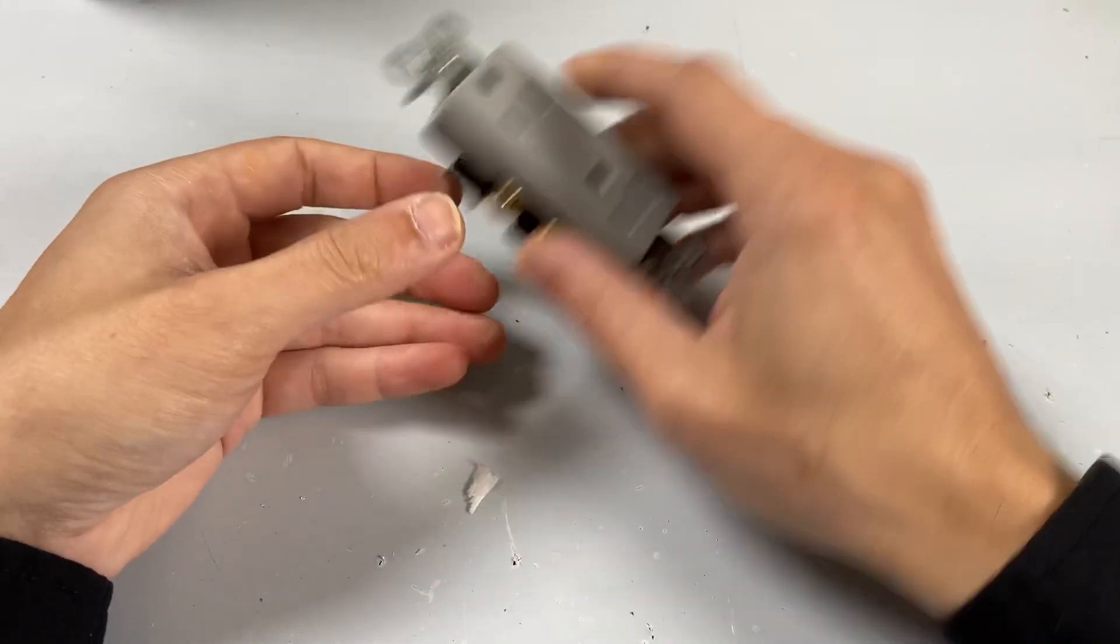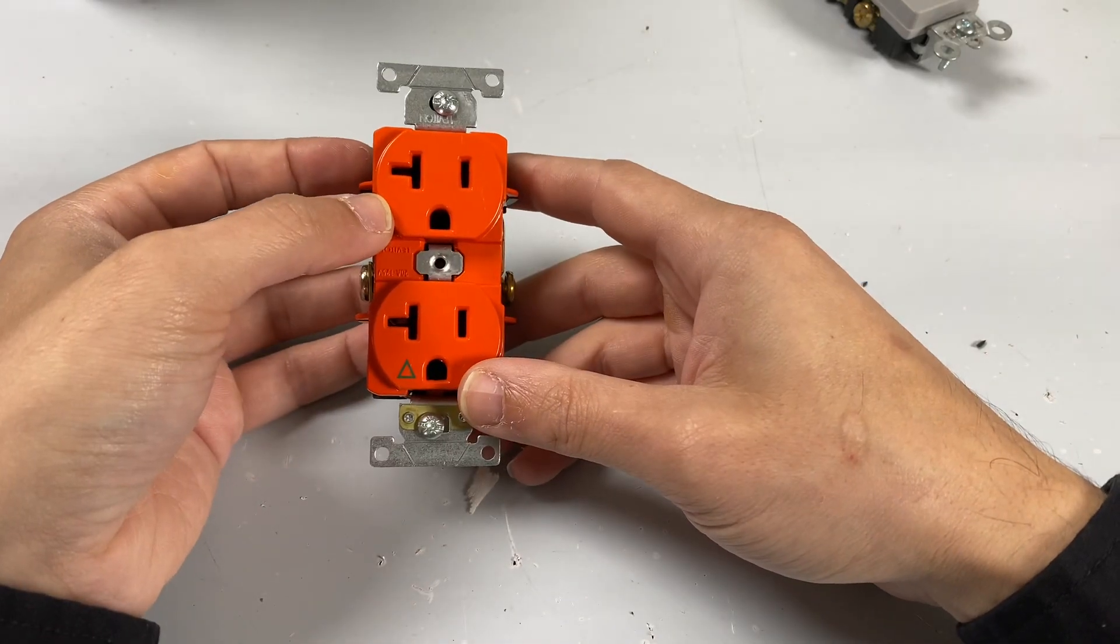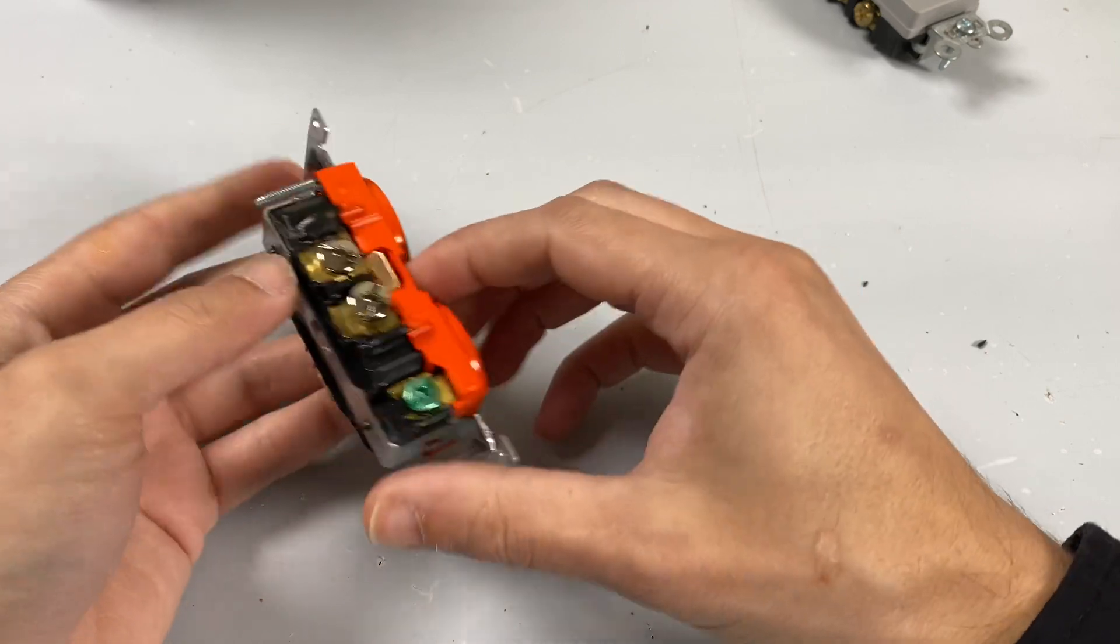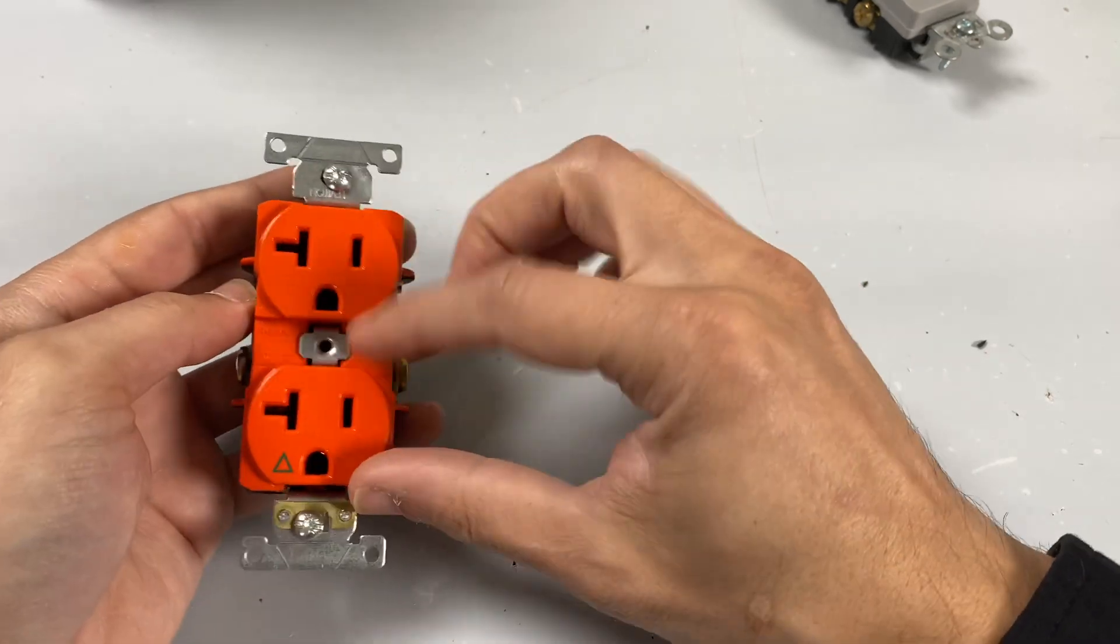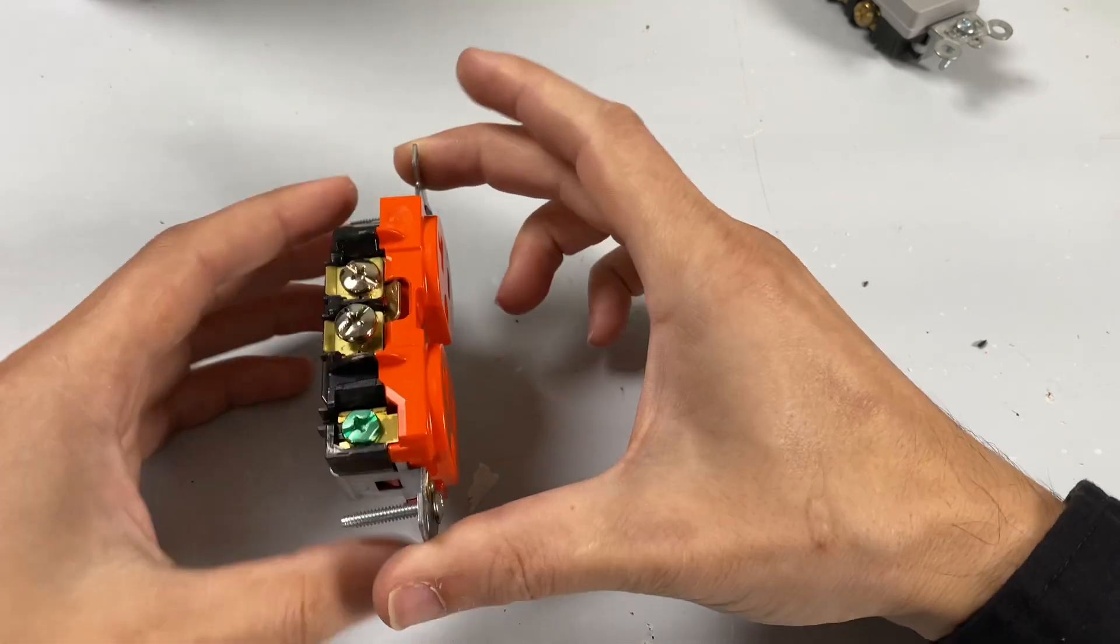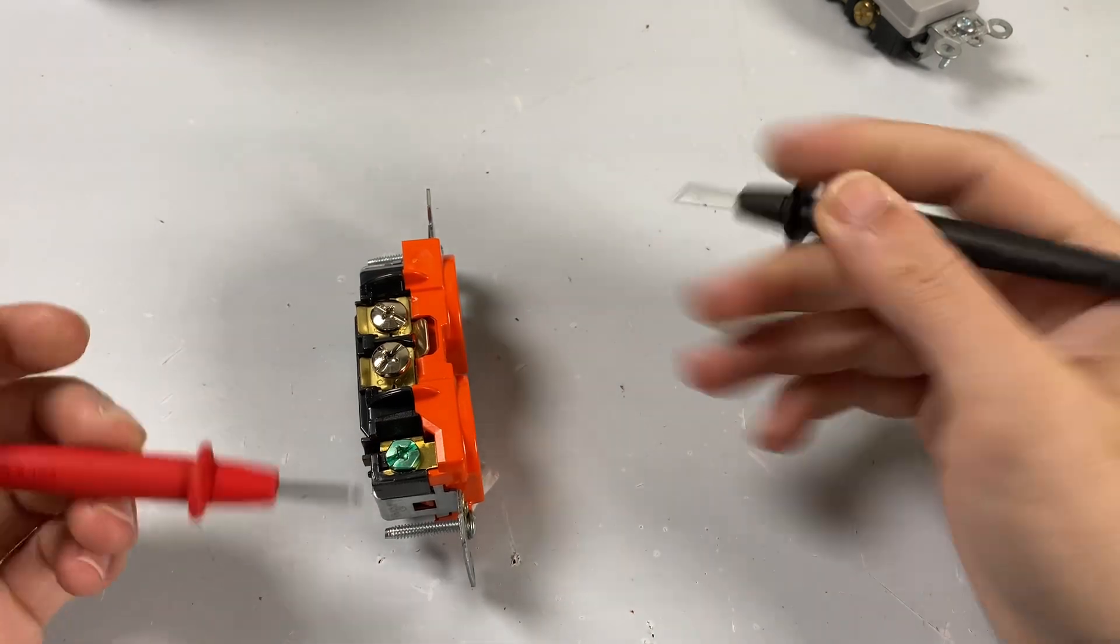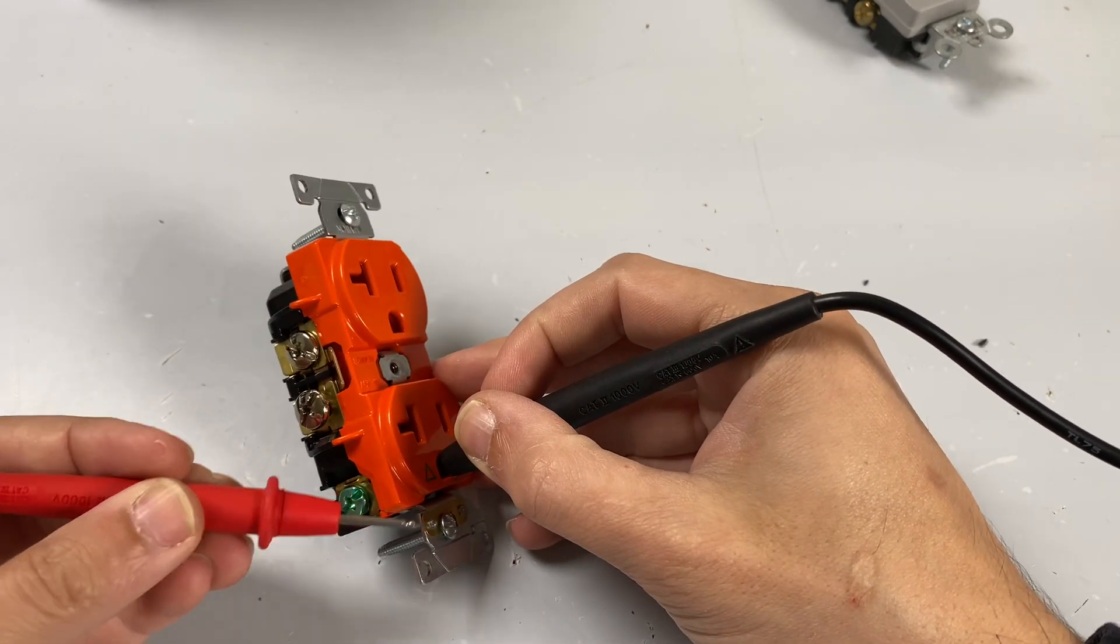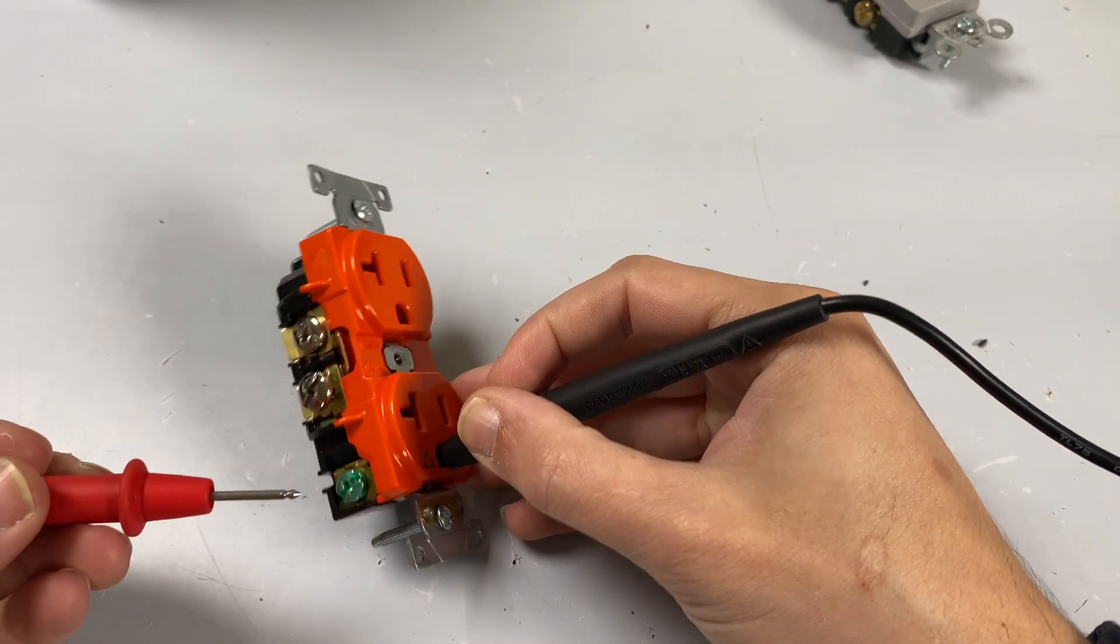The way that we get around that is we use what's called an isolated ground. What an isolated ground outlet is, is it separates this part of your outlet from the chassis. So if we take our multimeter in here and we touch our ground pin and our chassis, we don't get continuity, which means this is isolated.